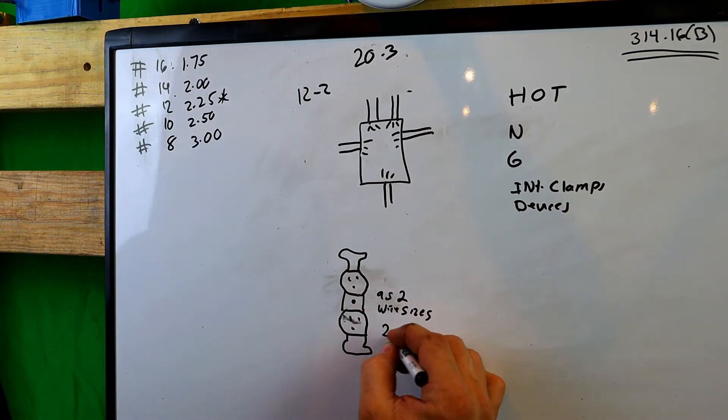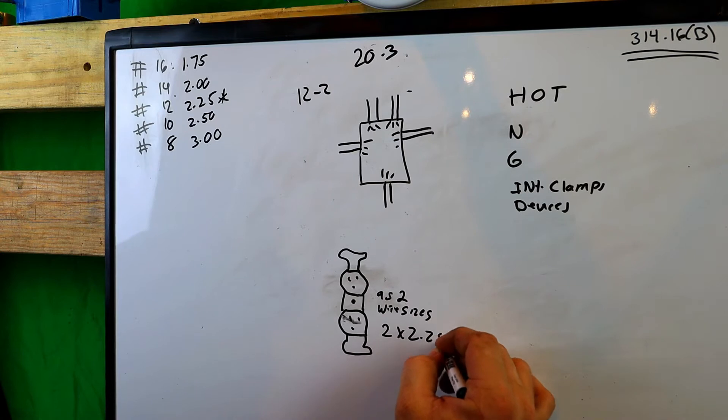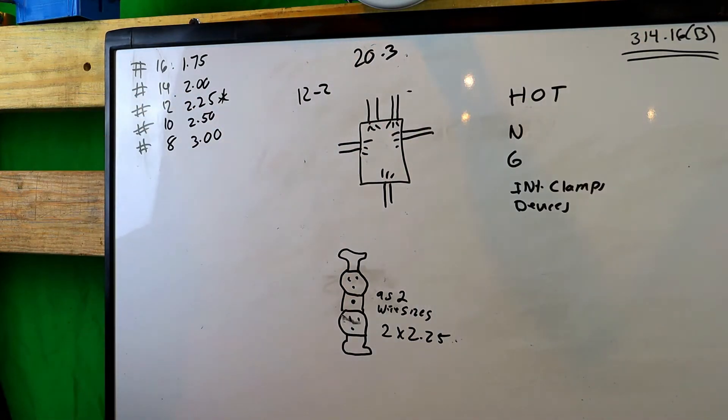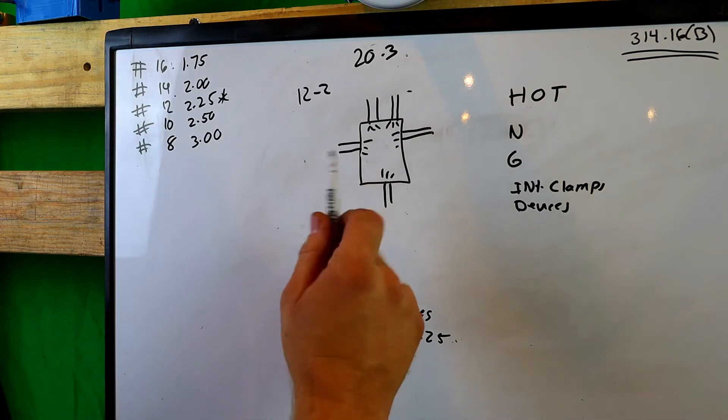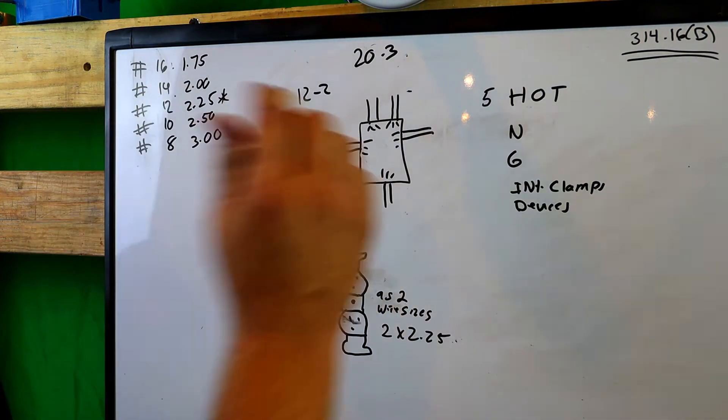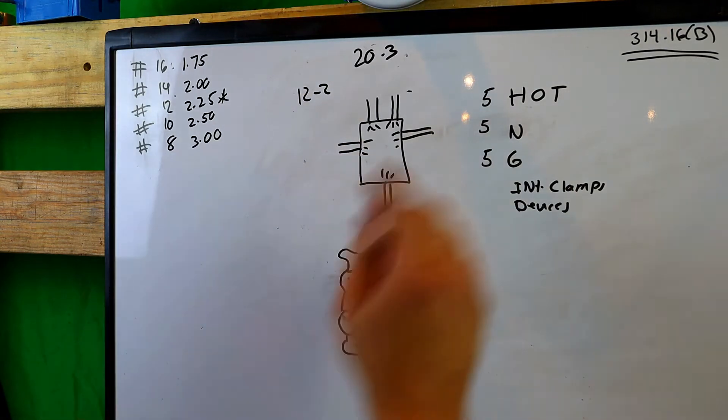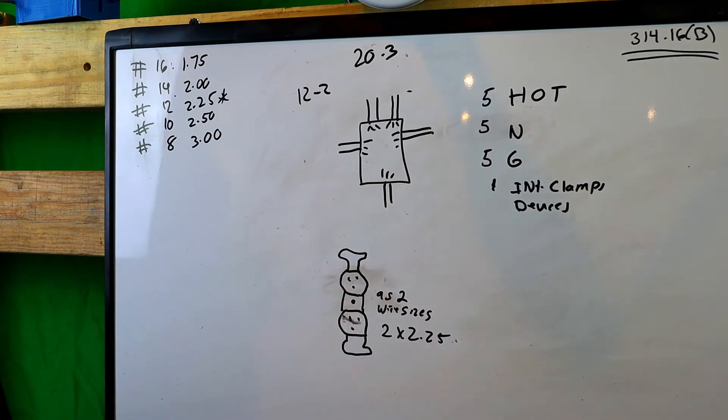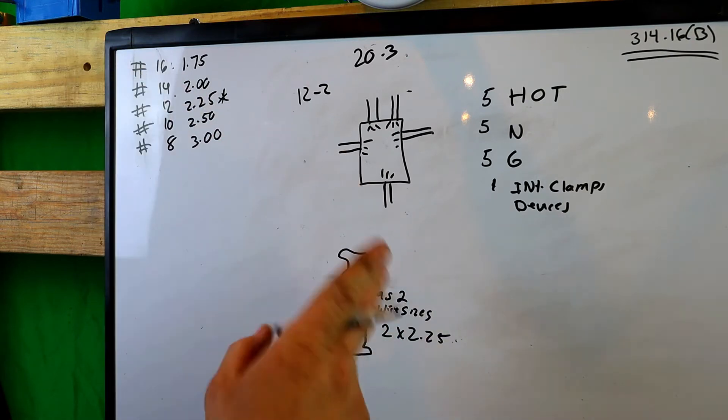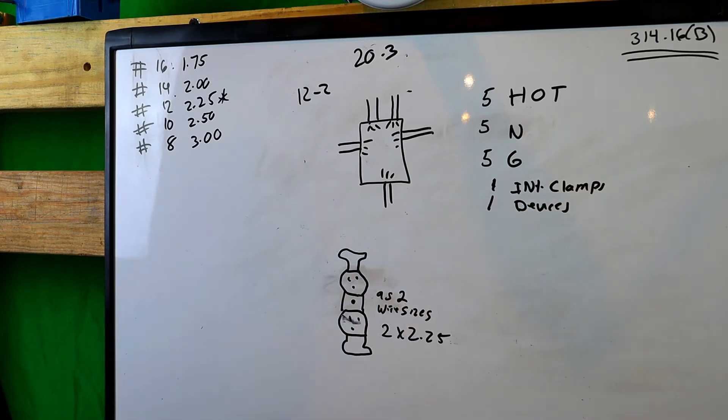Now we know we have one device. We have to count this device as two wire sizes. We know that everything here is going to be 12-2 romex, so everything in this box is 12-2. We know that our device is two times 2.25, and we can see that right here in the code book 314.16B. So we know that there's going to be 2.25 times two. We know that each romex has one hot - there's five romexes, so there's five hots. We also know that there's five neutrals in this romex, five grounds, one internal clamp because you only count the internal clamps as one, and one device. But we have to count each yoke strap as two wire sizes, so this will be 4.50 and we need to figure out the math.